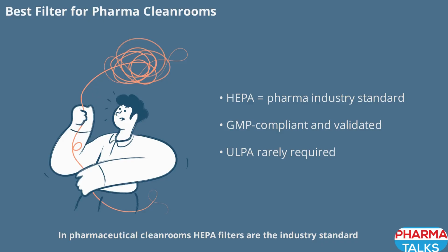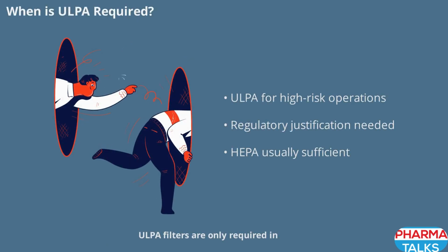In pharmaceutical cleanrooms, HEPA filters are the industry standard. They are fully compliant with GMP, ISO, and FDA requirements when properly installed, tested, and validated. ULPA filters are rarely mandatory in pharma settings, as HEPA filters provide sufficient protection for most applications. The key is to ensure that the chosen filter is validated and meets all regulatory expectations for the specific cleanroom class and process. ULPA filters are only required in situations where contamination risk is extremely high, such as high-risk sterile operations, semiconductor-like environments, or advanced biologics manufacturing.